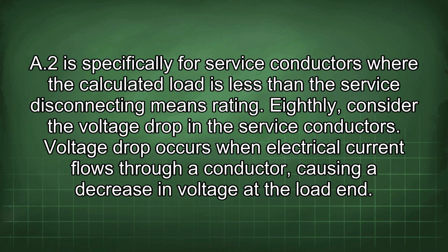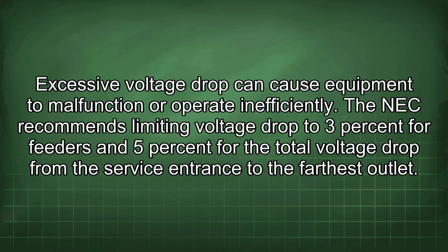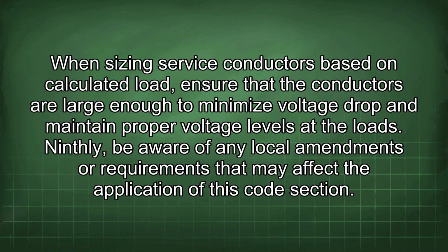Eighthly, consider the voltage drop in the service conductors. Voltage drop occurs when electrical current flows through a conductor, causing a decrease in voltage at the load end. Excessive voltage drop can cause equipment to malfunction or operate inefficiently. The NEC recommends limiting voltage drop to 3% for feeders and 5% for the total voltage drop from the service entrance to the farthest outlet. When sizing service conductors based on calculated load, ensure that the conductors are large enough to minimize voltage drop and maintain proper voltage levels at the loads.